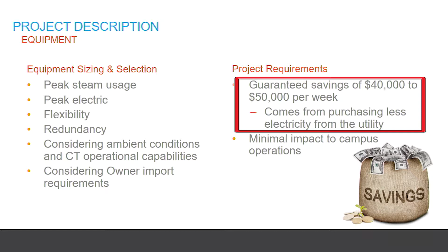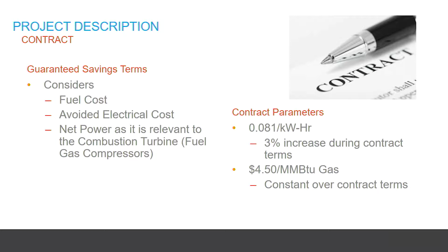Ultimately, this contract was developed under guaranteed savings terms. The tricky part of the contract was understanding what part of the auxiliary loads were associated with this new project. Dividing that up in the contract was a little messy, but ultimately for this project it was the gross power of the CT less the fuel gas compression power. The other aux loads, like boiler feed water pumps and such, were not considered in the guaranteed savings terms.